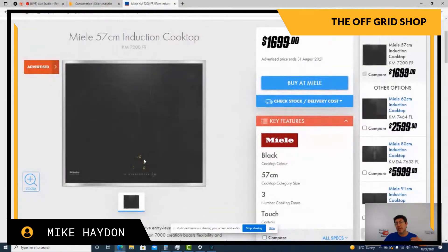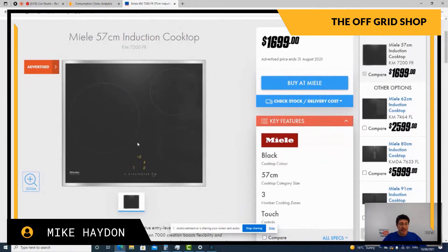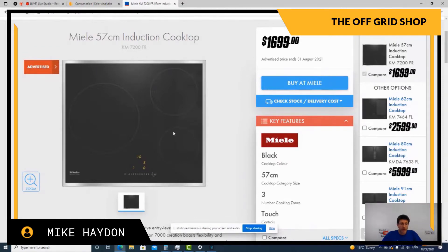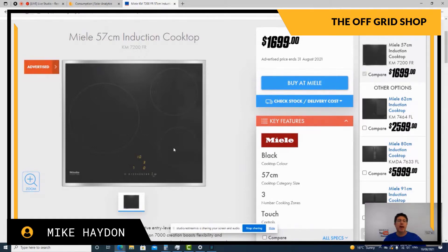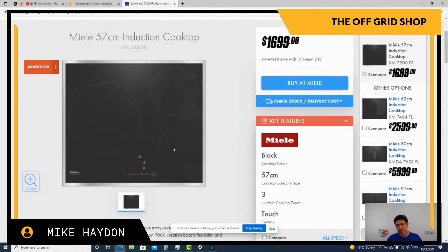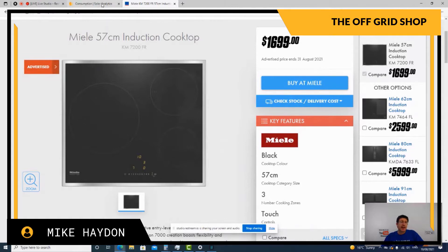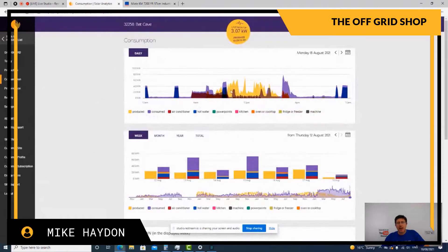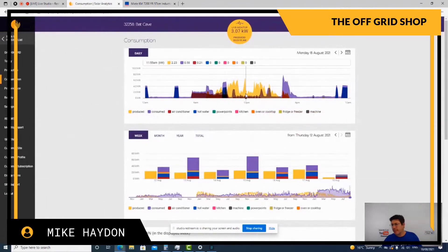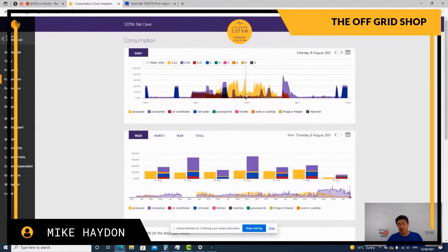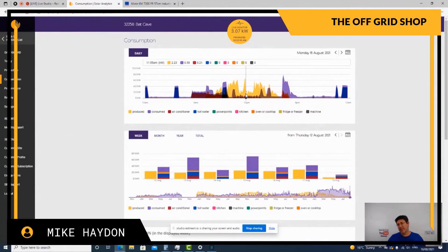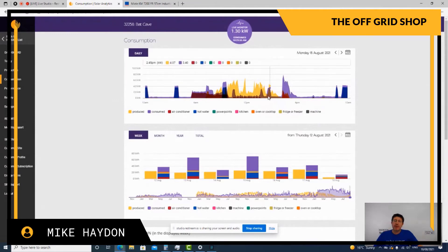And the reality is, even though I think this cooktop is seven kilowatts, when it is seven kilowatts with this cooktop, you've got all the things on at once. So you run them all, and you've got the boost function cranking to get there. So you actually have two boost functions. So you actually boost two of these at once. Now, just think about, is that something that you're going to be doing in a real world situation? Will you have all three things going? If you do, you might want a bigger inverter. That's what it all really comes down to, just think about how you use your appliances and how you cook your meals and things like that. The reality is the best thing you can do is, we go back to our solar here, the more you can do of a day in an off grid situation, I highly recommend most people have a grid connected inverter for an AC coupled on bigger systems. That gives you more usable power of a day. And you can do more things of a day. So if you are going to do an oven cook or a long cook or something like that, you want to maybe try and get in the oven when the sun's still out so you're not doing it from your battery.